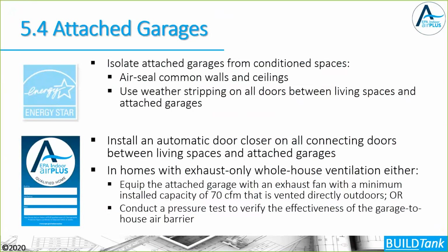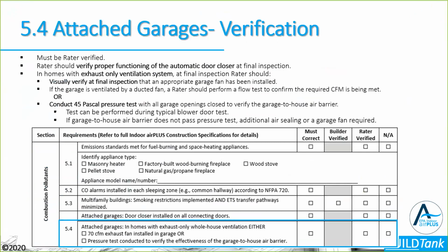So you can't visually see if the garage is actually separated from the house. You've got to test it, you've got to ensure it, and it's a pretty important part of this program to ensure that you get that added level of safety and health by clearly separating the house from any attached garage here. From a verification perspective, it's laid out here on the verification checklist.